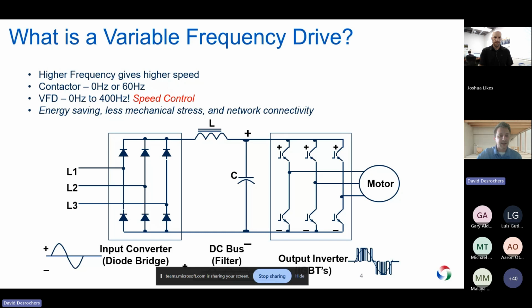Starting from the far left, we've got 3-phase incoming line power going in, and then that gets rectified through some diode bridges here. Then that goes into the center where you see the L and the C. That is our DC bus. The HP600, the primary flagship HVAC drive we're going to discuss today, actually includes a split link choke inside it as standard. Right off the bat, this will reduce some of the harmonic distortion that drives can create. Finally, we take that DC bus and invert it on the right side using these fancy switches called IGBTs. That recreates what is basically a simulated sine wave. This sine wave can then run any induction motor. We're seeing permanent magnet motors come onto the scene as well too. Yaskawa can handle both of them.